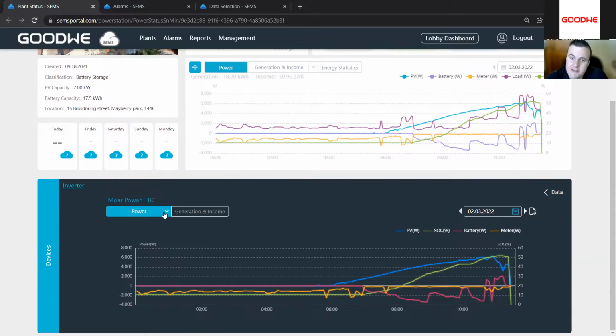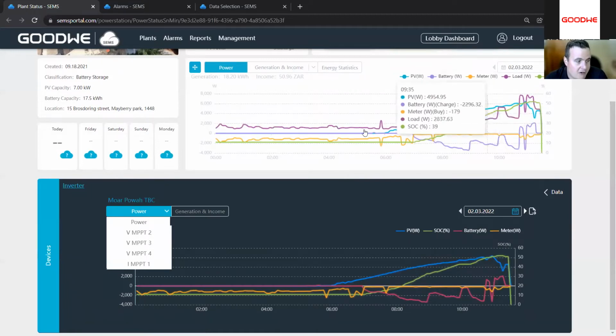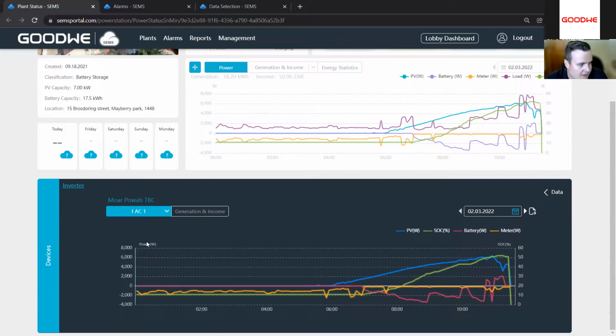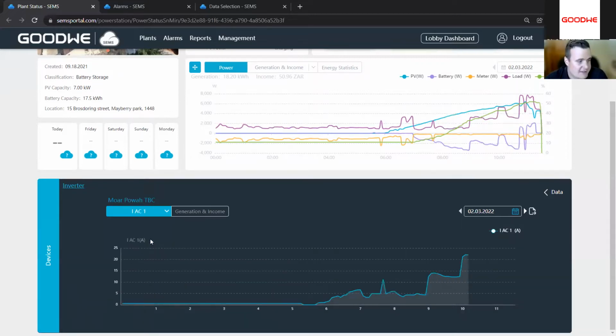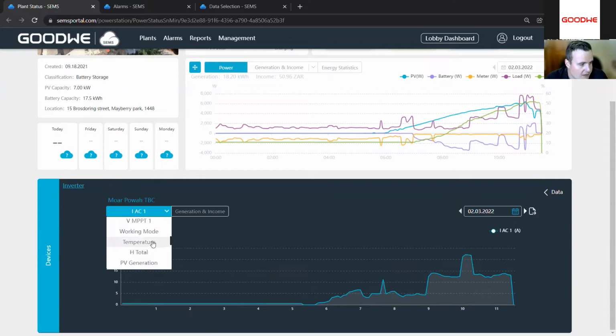Here in the curve, we've got a drop-down list. In the drop-down list, you'll see power, which is the same power graph as above. You can see the individual information from the MPPTs, the voltages, the currents, the voltage of the utility, the currents of the utility, like IAC. IAC is the output to the utility terminal of the inverter, so how much current it's outputting to the utility side of the inverter. So yeah, it's a lot of information for us.